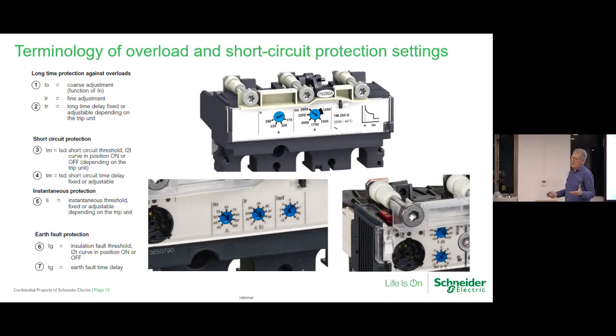A lot of our trip units are all electronic now, so they're much more adjustable, and the word selectivity is what it's about. We can select more settings to get closer to the load and protect the network better. This one is a base level one, IO, IR, and ISD in the electronic version, and you can see there's a port and it can be tested. These two work together to set up the thermal, and then ISD is the short circuit, short delay. Over here we've got an advanced trip unit. There are only two settings in here, IR and ISD, and to the right, which you can't see, is just a digital face. You go in there and set all the other parameters, all these other time delays, instantaneous, earth fault if you had it.